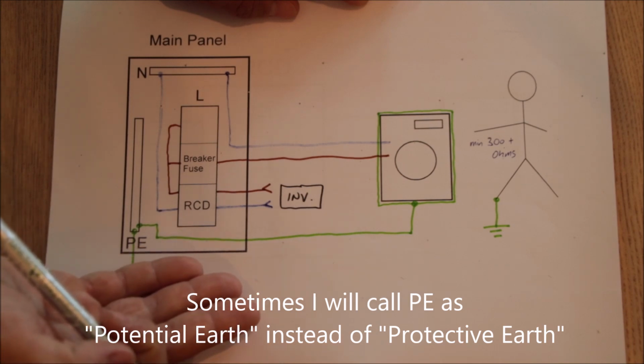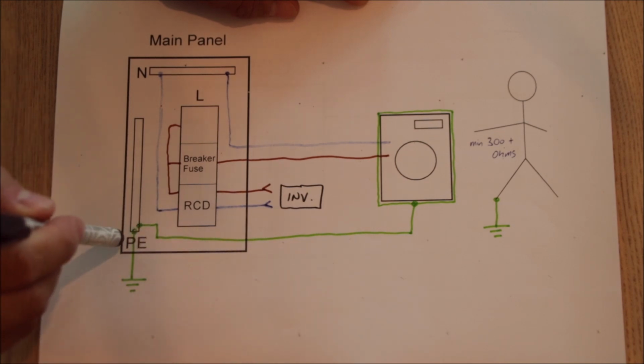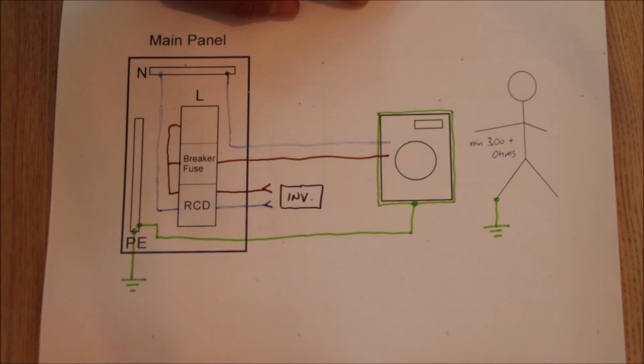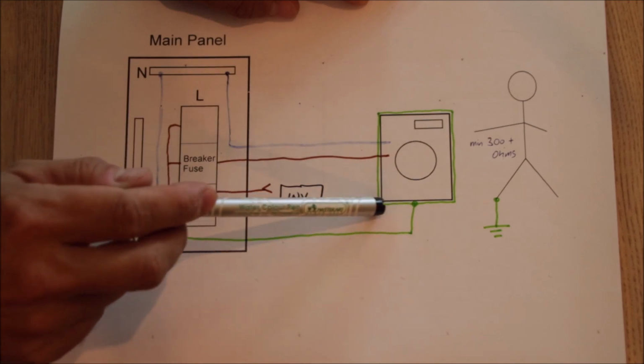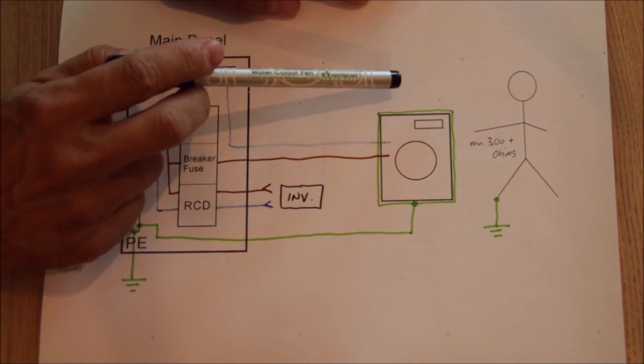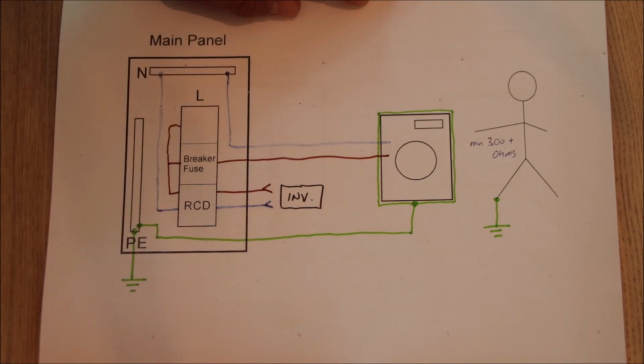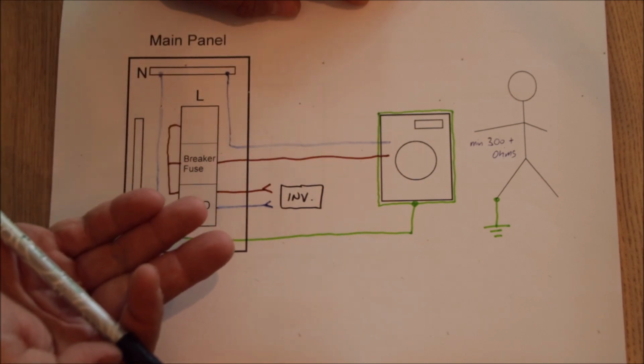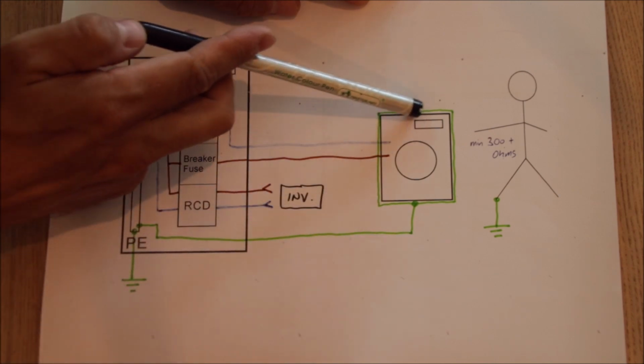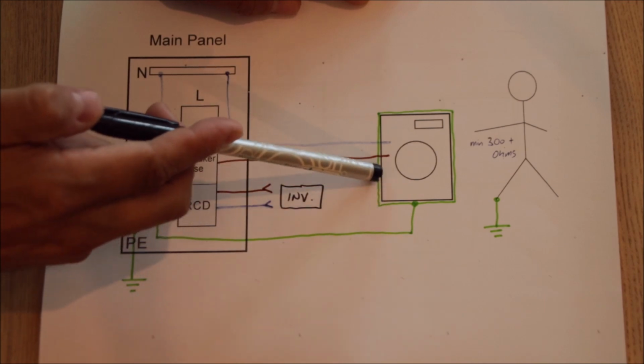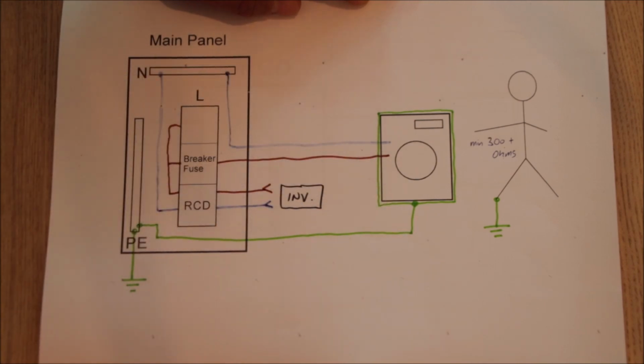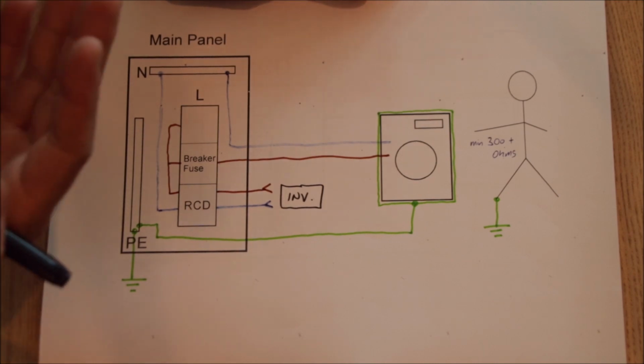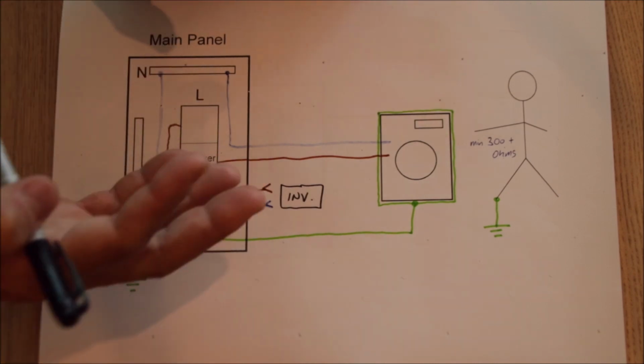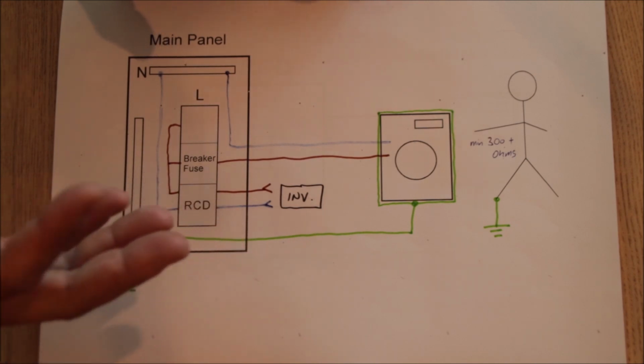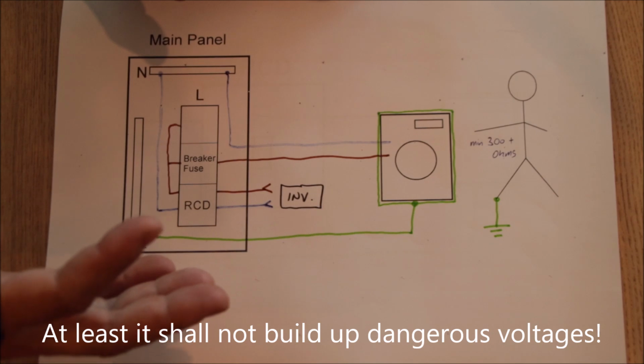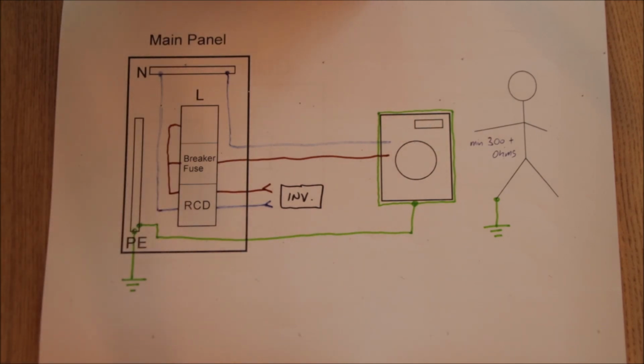Everything on that circuit must have potential earth or a zero potential. As you can see, the PE is actually acting like a protective shell around our electric devices. Big appliances, devices that typically will have a metal shell, and that shell will be connected to our PE. So whenever a fault inside the device occurs, the outside shell shall always remain on zero potential. That is very important in the earthing systems.